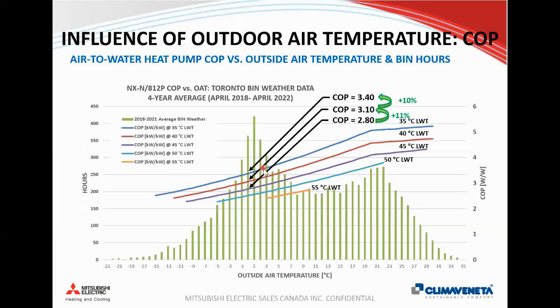If we look at an arbitrary point of 0 degrees ambient, on a milder day like it was yesterday in Toronto, today's about -6. If we're designing with a 45 supply temperature, our COP is 2.8, so that's still pretty good. But if we're able to drop that down by 5 degrees Celsius, we can increase the efficiency by about 10% and have a COP of 3.1. Or if we're designing with 35 degrees, we can have a 20% improvement and have a COP of 3.5, which makes a lot of sense if we're comparing that to an electric boiler.